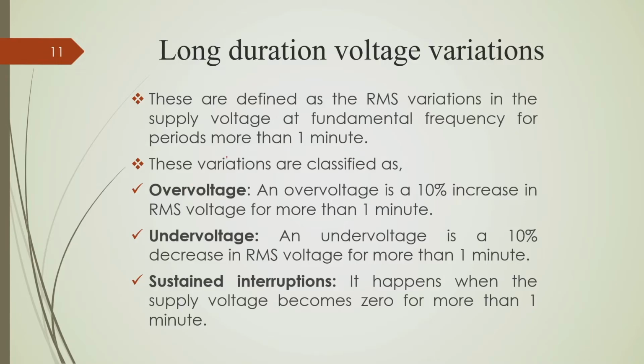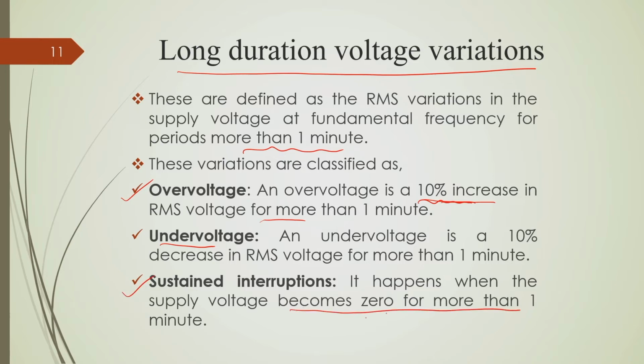Okay. Similarly, long duration voltage variations have a duration of more than 1 minute. If the RMS value of the voltage is reduced by 10% or maybe 15-20%, we call it under voltage, and if the RMS value rises by 10% or 15%, we call it over voltage. And sustained interruption is when supply voltage becomes 0 for more than 1 minute. It is similar to short duration interruption, but here the duration is more than 1 minute.